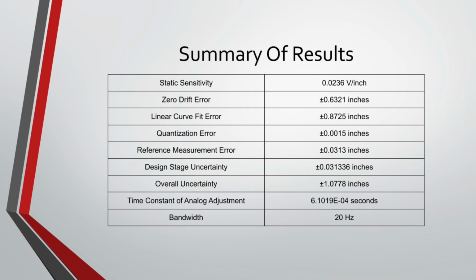From these calibrations, we found the static sensitivity to be 0.0236 volts per inch over the tested range, but we expect this sensitivity to hold over the maximum range of the sensor as it appears to be very linear. The found time constant for the analog adjustment circuitry is interesting but not relevant to the sensor's bandwidth, which is 20 Hz, or the inverse of its cycle time.